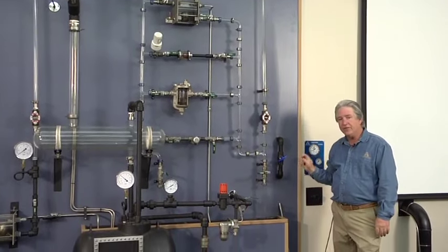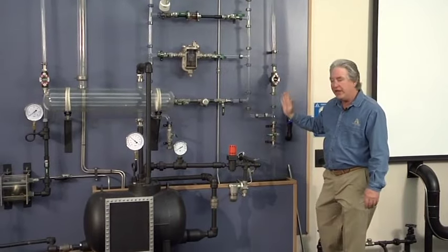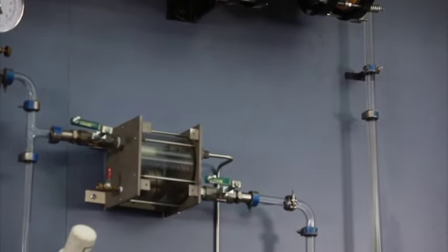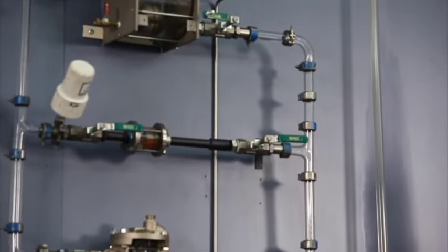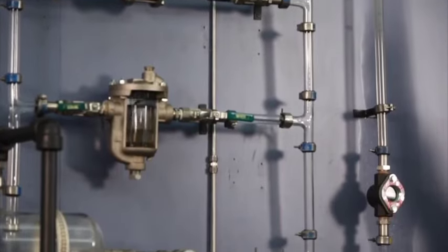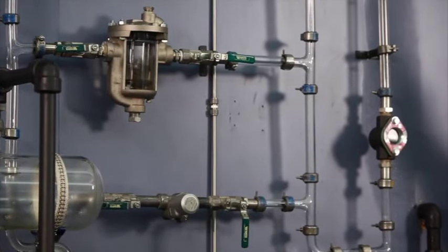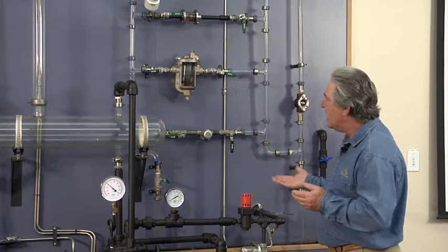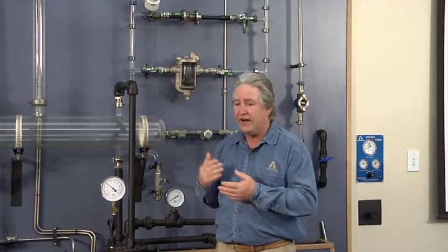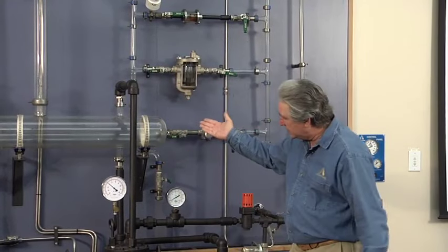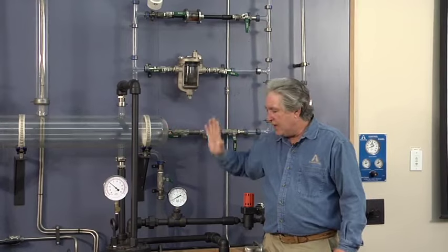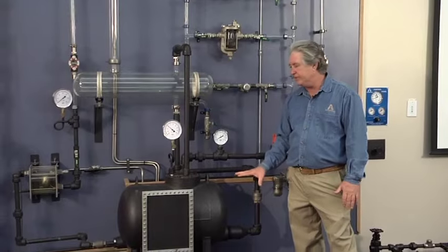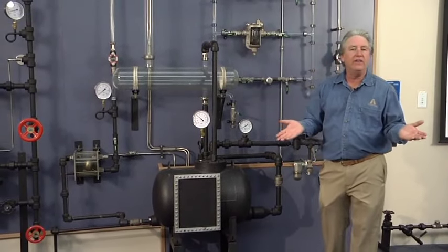The other thing we always have to remember is not only do we have liquid head in the vertical rise, but we also have the pressure that exists in the condensate header itself that we run, usually in an overhead return scenario. What we want to do now is I want to slowly actuate a valve that will allow us to observe our pumping trap system and how we can optimize those exchangers by allowing them to run in the lowest possible pressure.